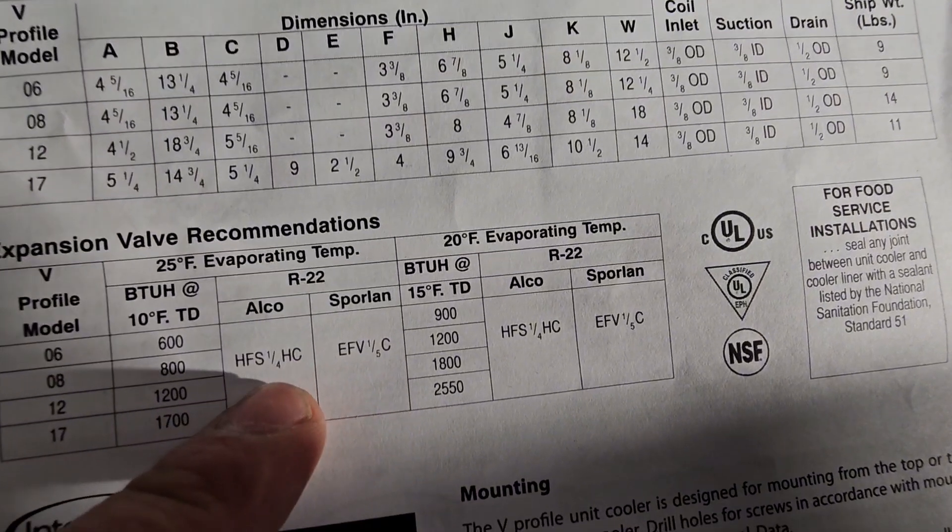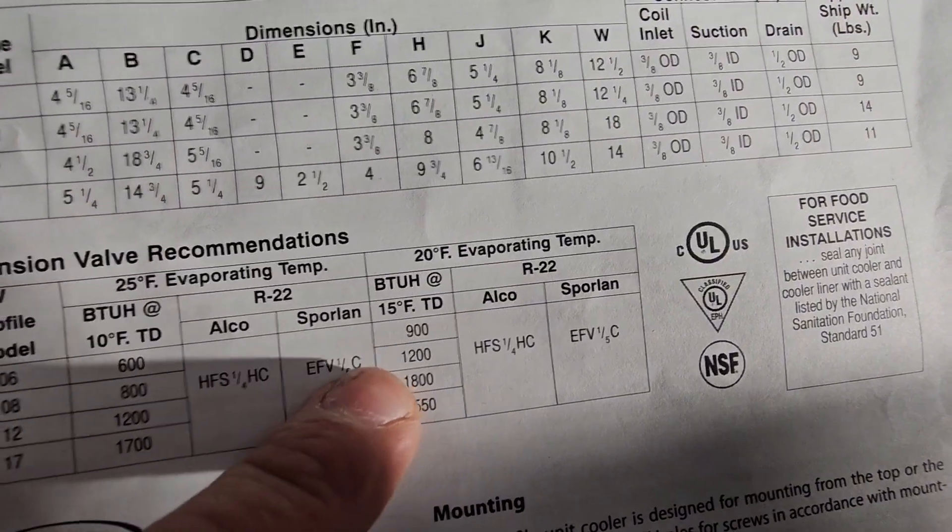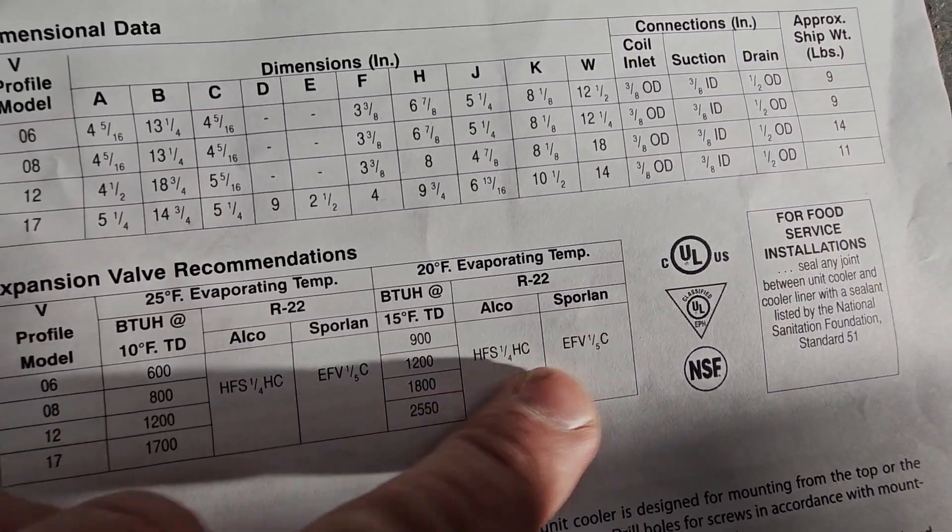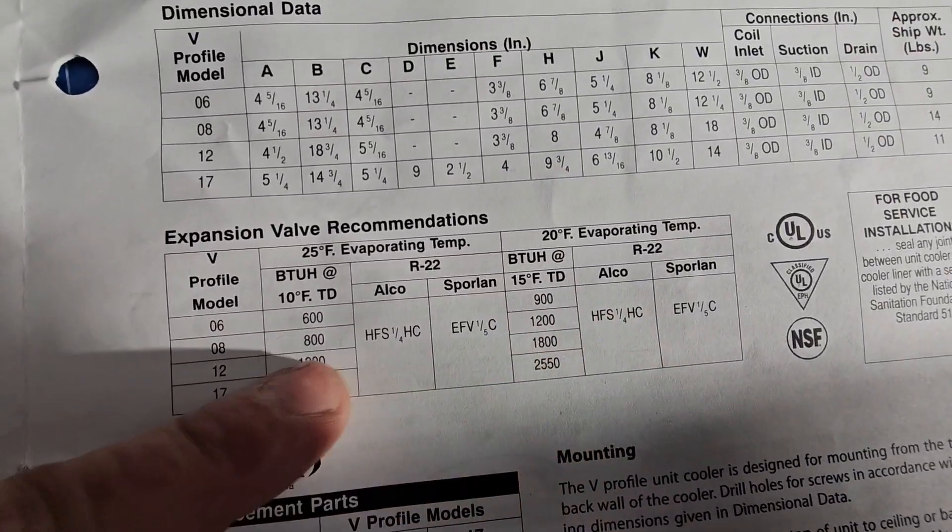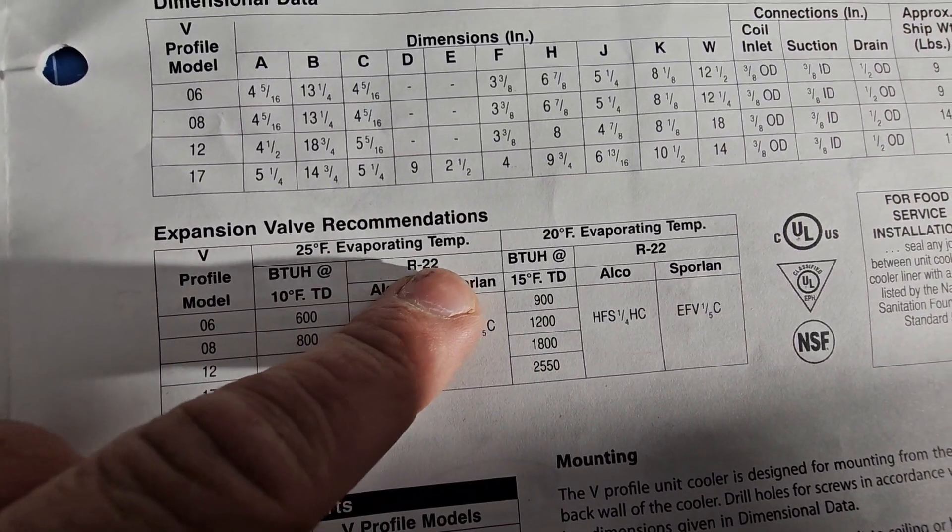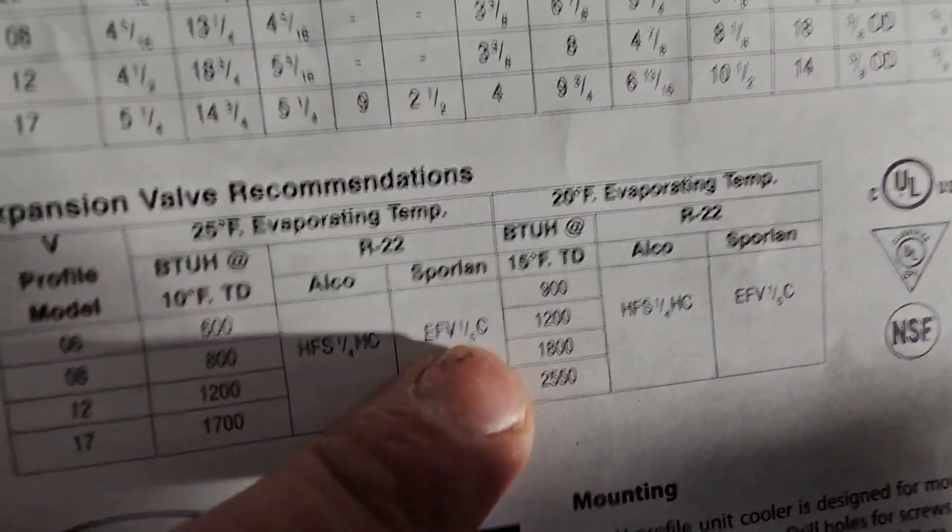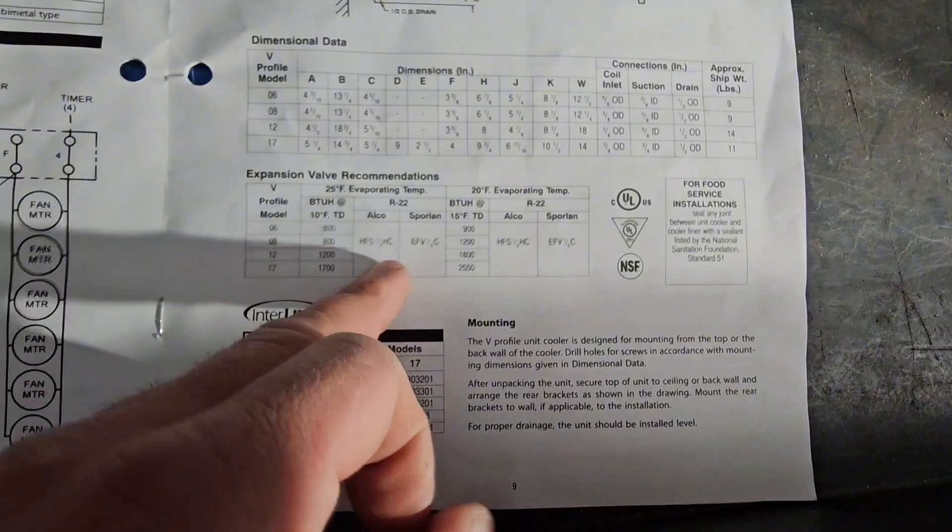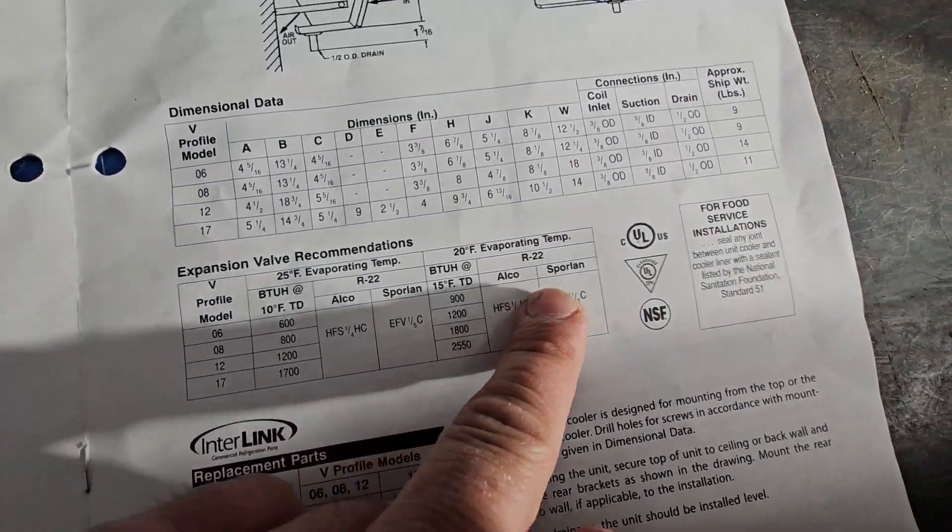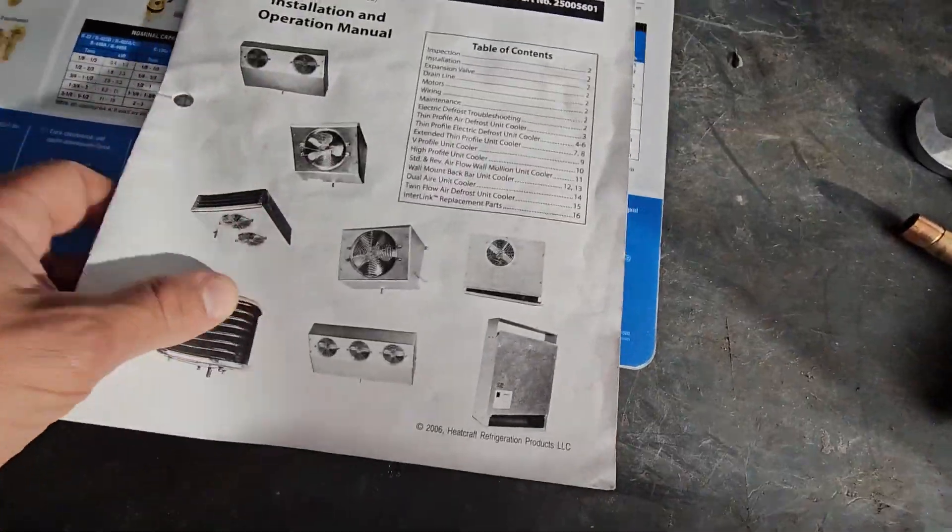And regardless, this is rated for R22. You need a quarter ton or a fifth ton valve for either, for both TDs. It doesn't matter what refrigerant you're using, you need a quarter ton valve or a one-fifth ton, which is just pretty much the same thing.